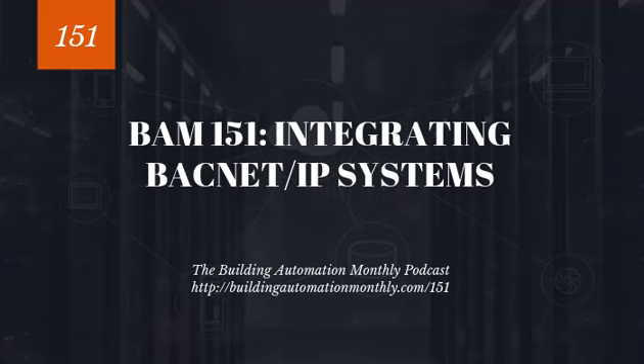We understand where commands and responses, those are the primary things. Now, in some cases, we'll call them request response, because that's technically the terminology that the BACnet protocol uses. You actually have your, what's the word I'm looking for here? Your services. You have your services like write property and read property, and then you have the request response from those.